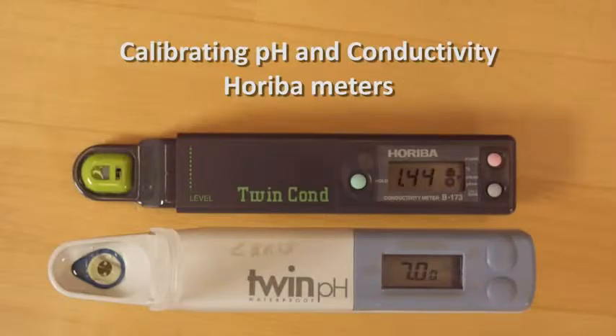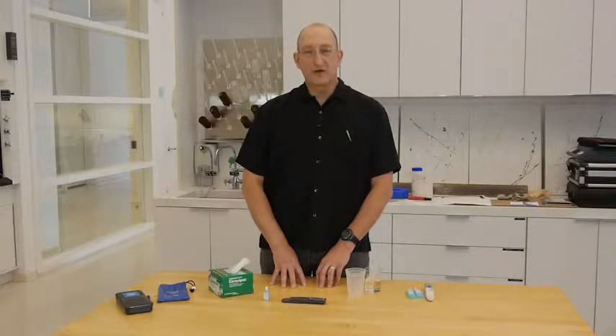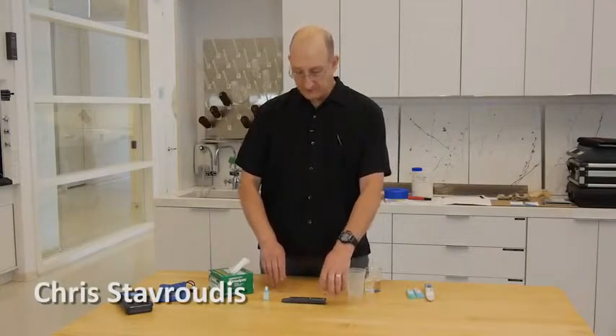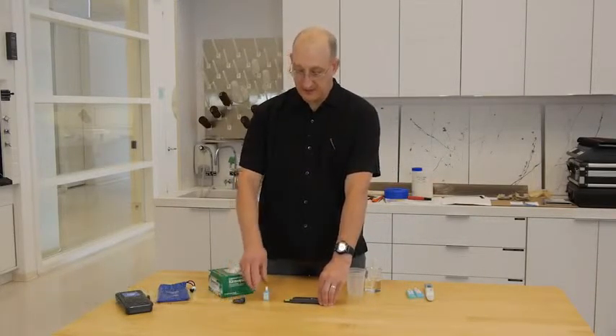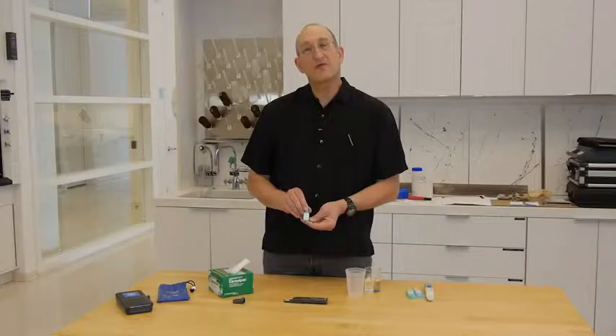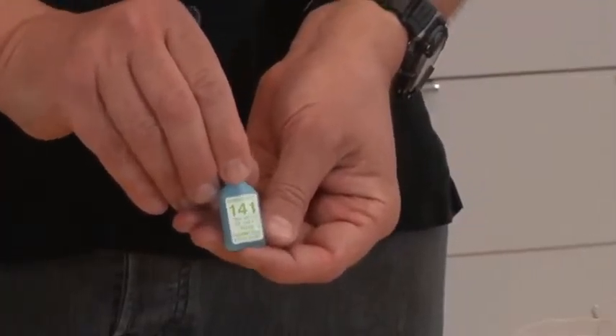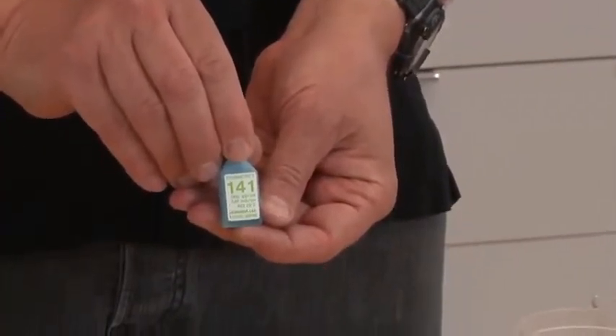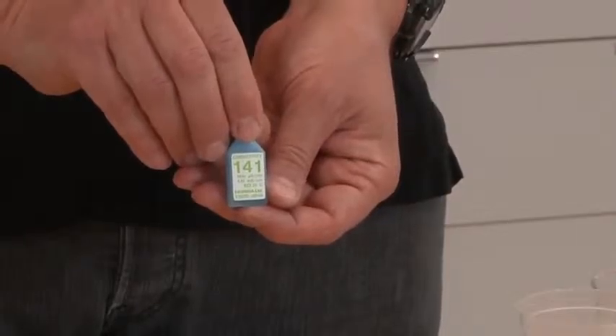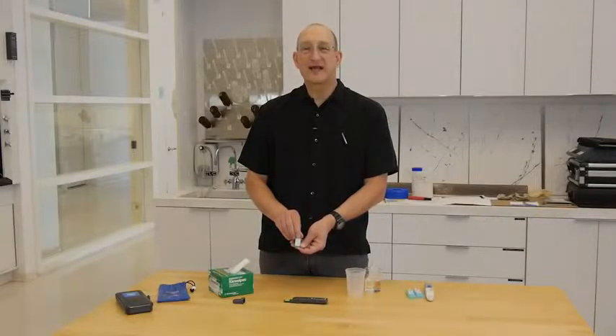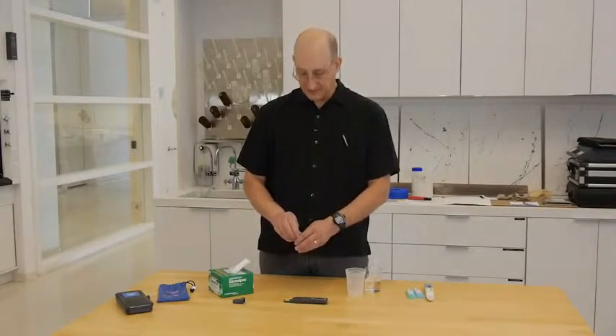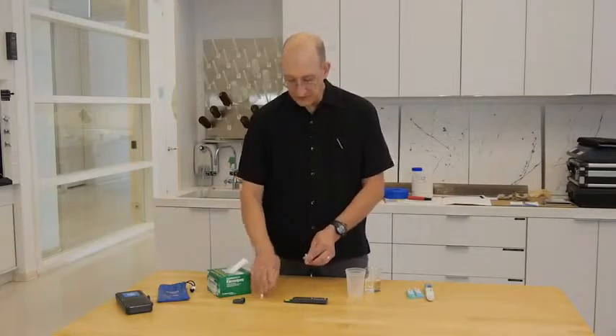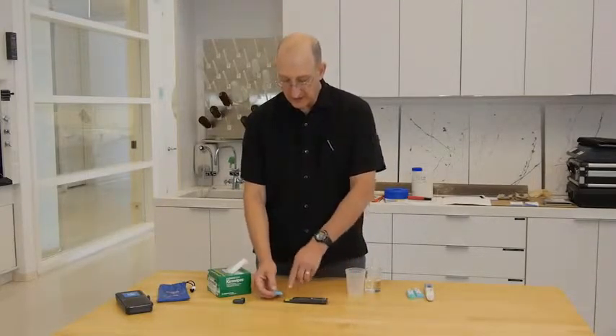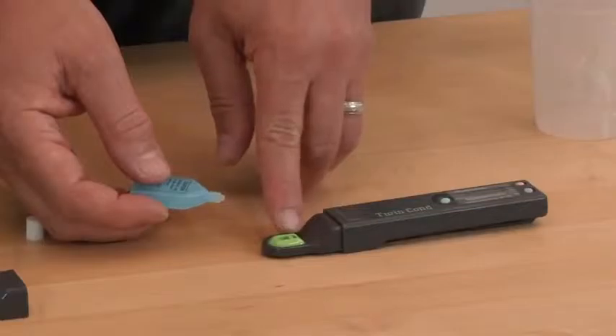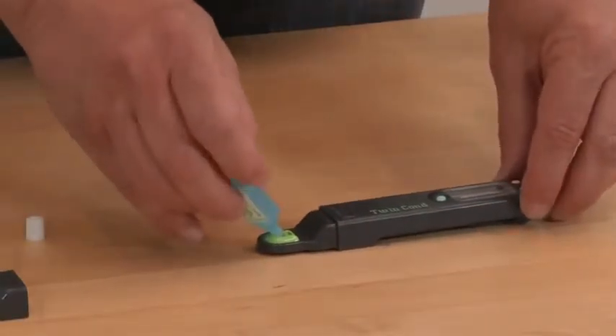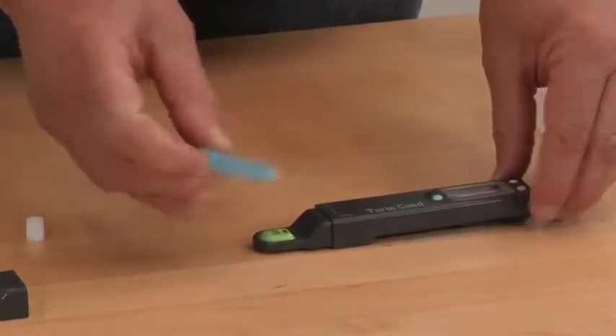To calibrate the Horiba conductivity meter, we want to start with turning the meter on, removing the protective cap, and we'll use a 141 calibration solution, which is 1.41 millisiemens per centimeter, or 1,410 microsiemens per centimeter. The sample well is this little green thing.